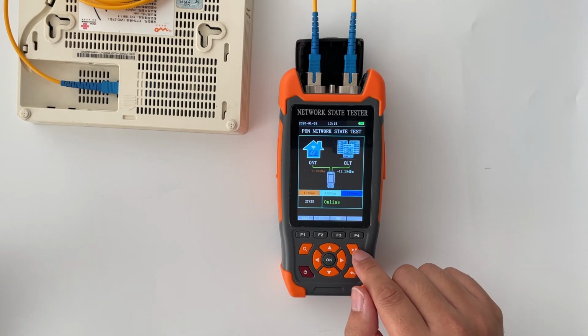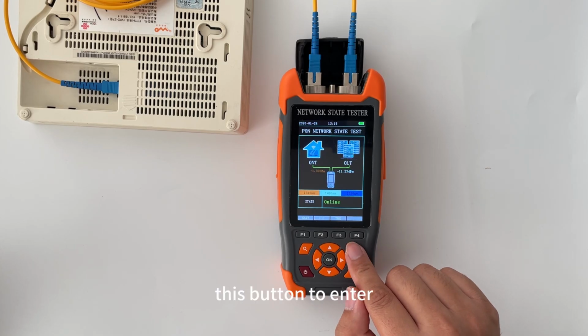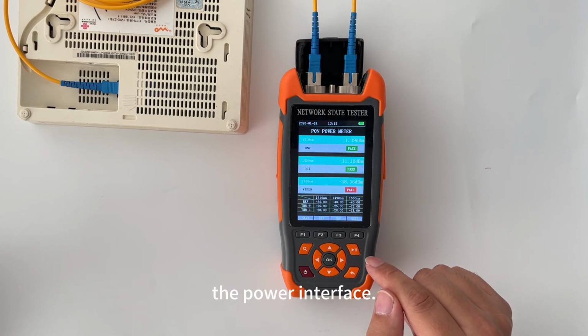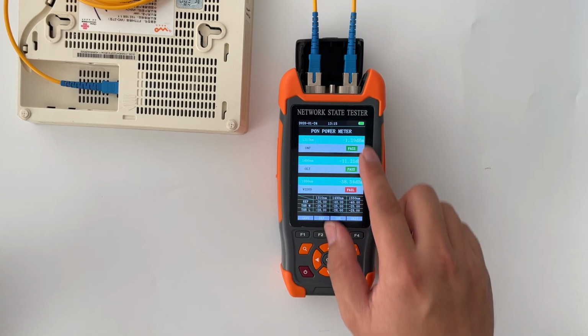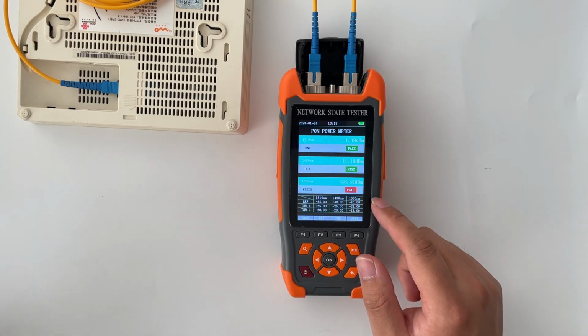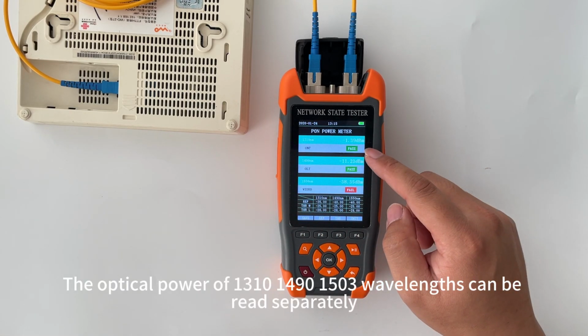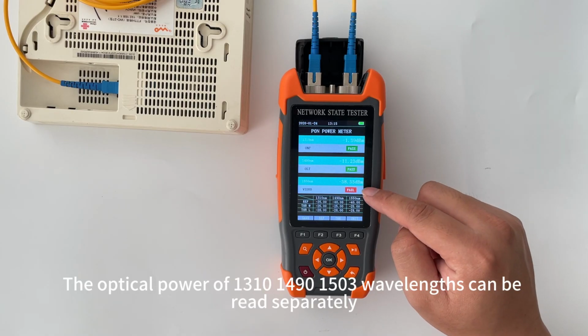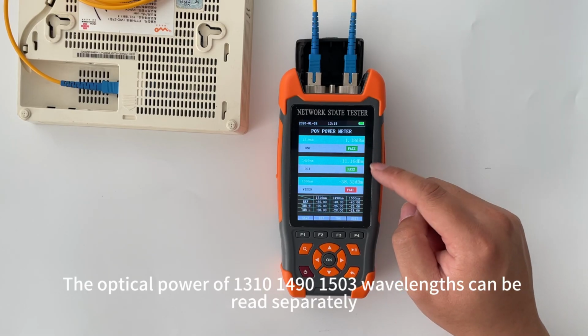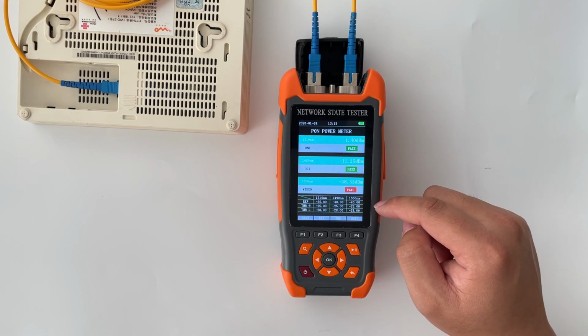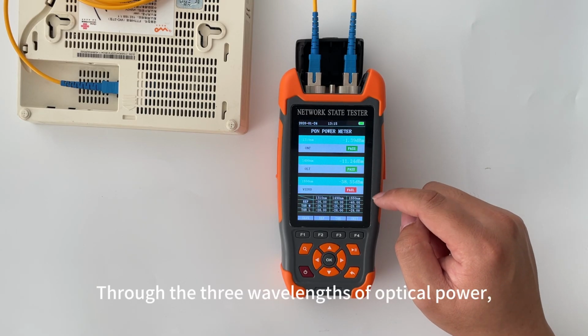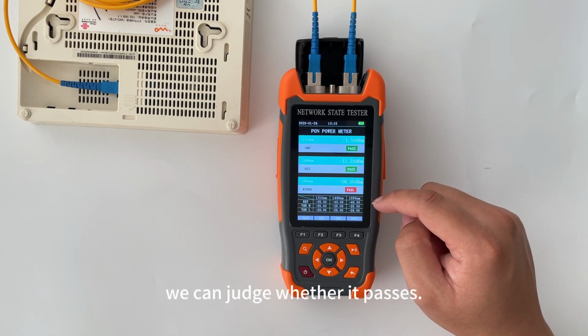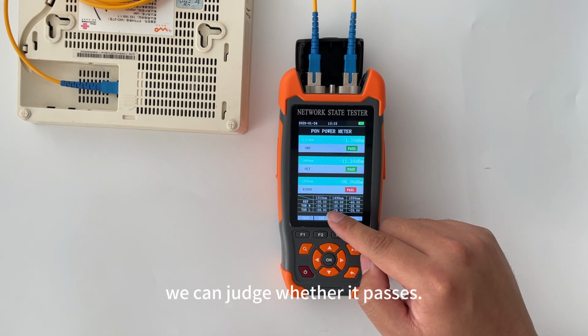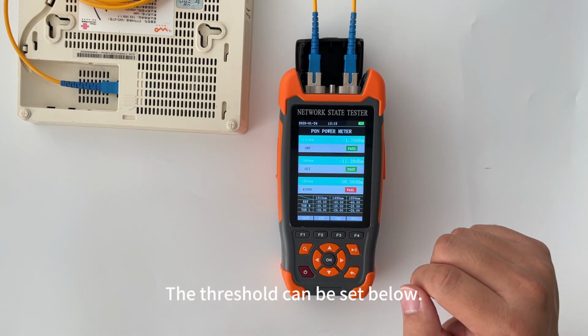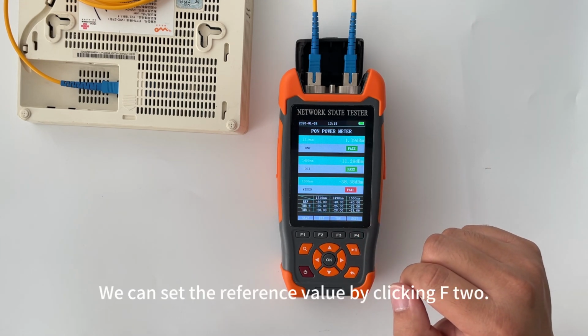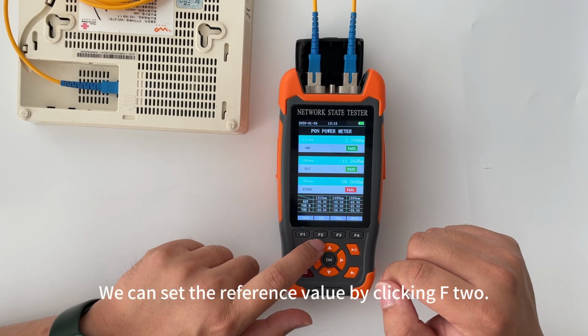We click this button to enter the power interface. In the power interface, the optical power of 1310, 1490, and 1550 wavelengths can be read separately. Through the 3 wavelengths of optical power, we can judge whether it passes. The threshold can be set below. We can set the reference value by clicking F2.